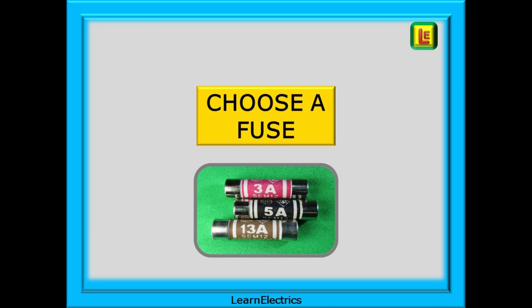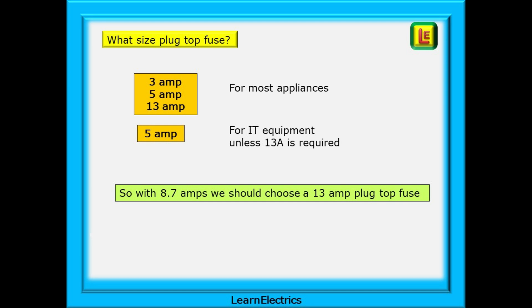But how do we go about choosing a fuse? It's bad practice to fit a 13 amp fuse for everything — we should always try and choose a fuse close to the actual working current. A bedside lamp, for instance, only needs a 3 amp fuse. There used to be seven different fuse sizes for your everyday plug top, but manufacturers have stopped making certain sizes on economic grounds. The industry is standardising on three sizes: 3 amp, 5 amp, and 13 amp. All we need to do is choose the size equal to or just above the current demand of the appliance. Most IT equipment should come with a 5 amp fuse as standard, and this is often printed onto the computer plug and lead. So based on this, with 8.7 amps in the last example, we should choose a 13 amp plug top fuse.